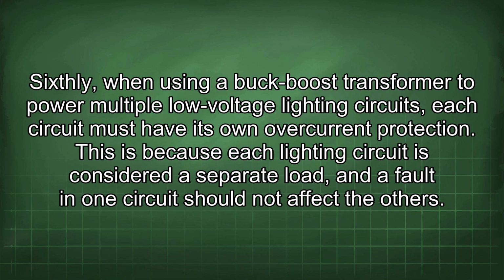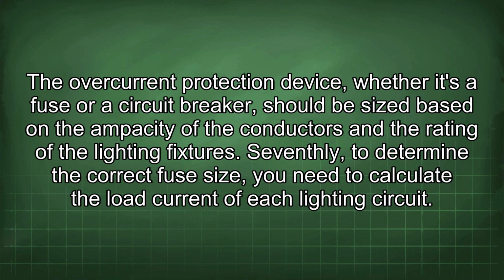Sixthly, when using a buck-boost transformer to power multiple low-voltage lighting circuits, each circuit must have its own overcurrent protection. This is because each lighting circuit is considered a separate load, and a fault in one circuit should not affect the others. The overcurrent protection device, whether it's a fuse or a circuit breaker, should be sized based on the ampacity of the conductors and the rating of the lighting fixtures.